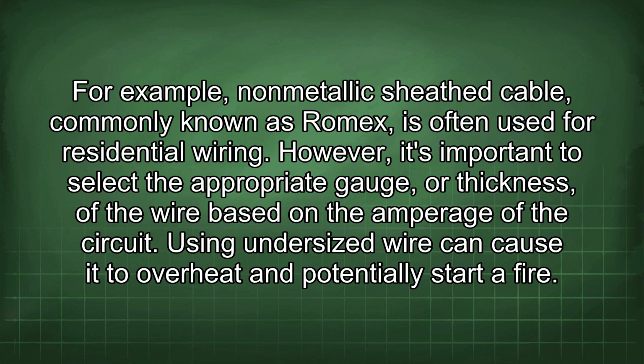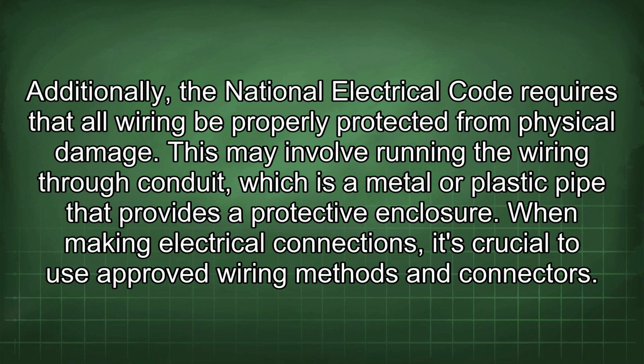For example, non-metallic sheath cable, commonly known as Romex, is often used for residential wiring. However, it's important to select the appropriate gauge or thickness of the wire based on the amperage of the circuit. Using undersized wire can cause it to overheat and potentially start a fire. Additionally, the National Electrical Code requires that all wiring be properly protected from physical damage. This may involve running the wiring through conduit, which is a metal or plastic pipe that provides a protective enclosure.